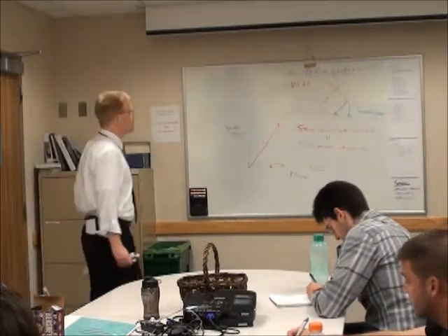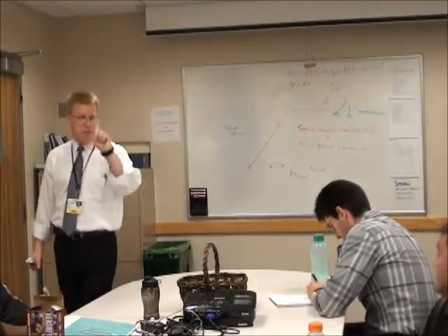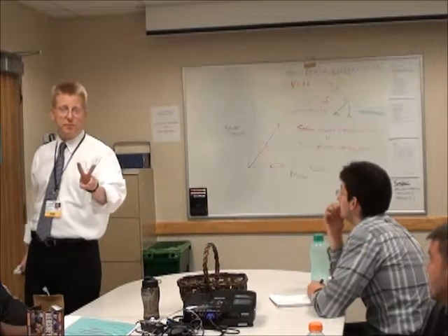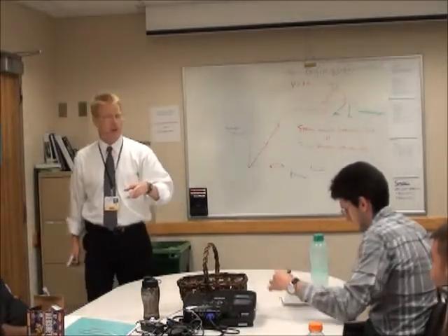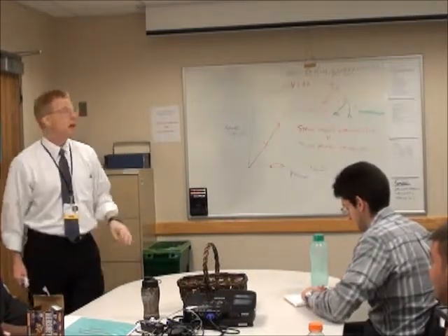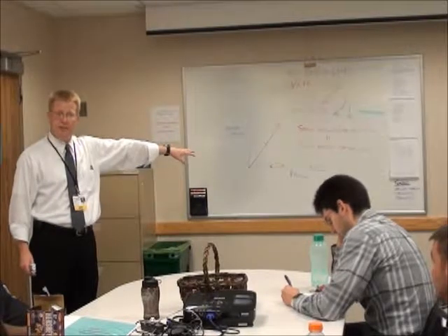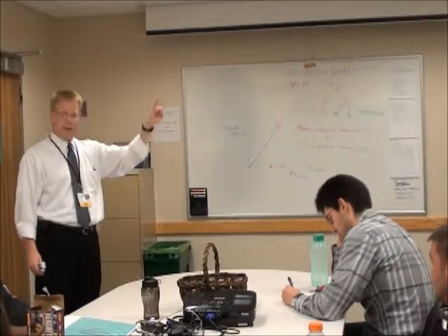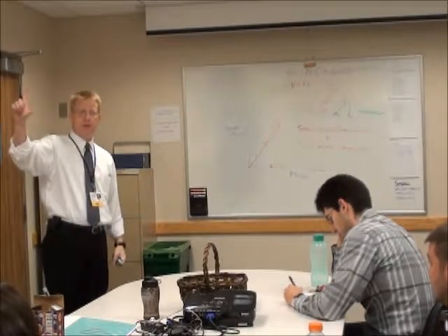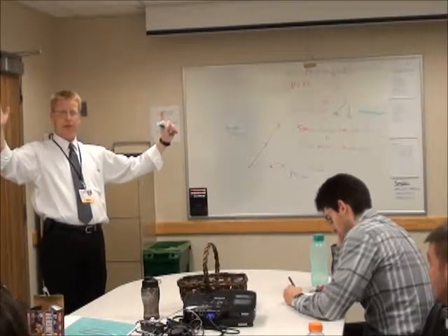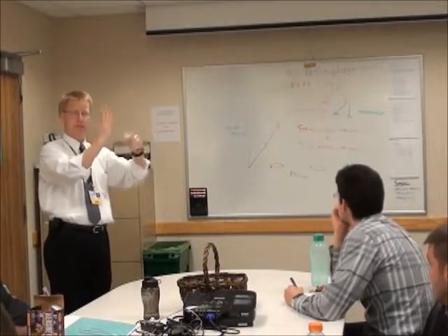Okay? So how do we measure these things? There's 2 ways. The cheap way and the expensive way. I like the cheap way, but I use the expensive one as well. Here's the cheap way. Look at the A-line. There's a pulse pressure on the A-line, right? Systolic, diastolic is right there. So what you can do, and you guys have all seen me do this, you walk up, you change the sweep speed on the A-line, so it crams a bunch of heart rates right together.